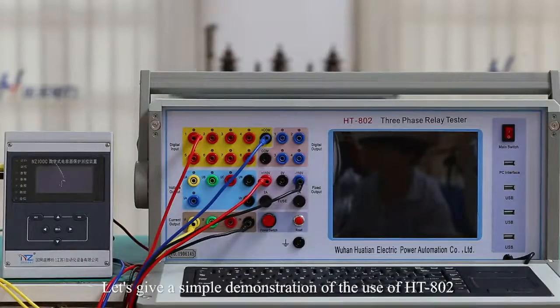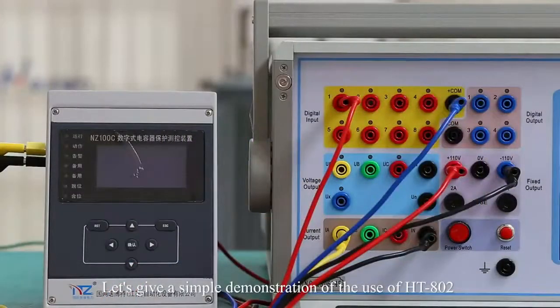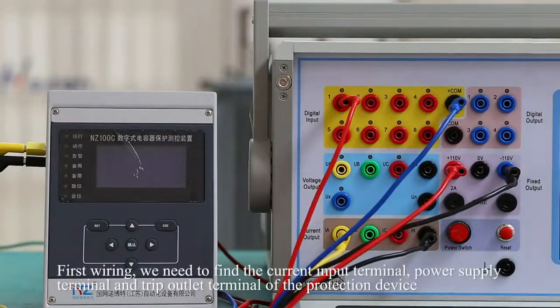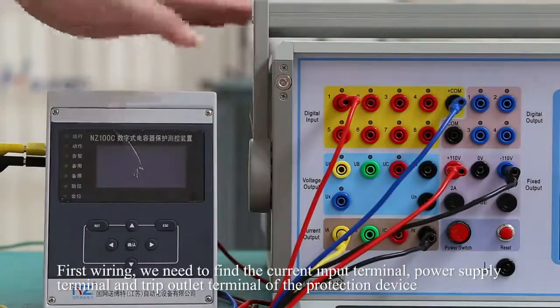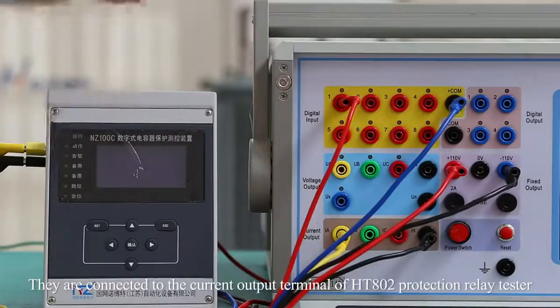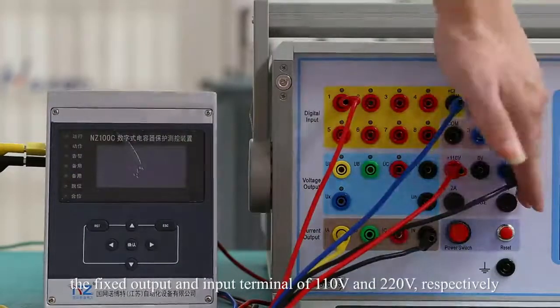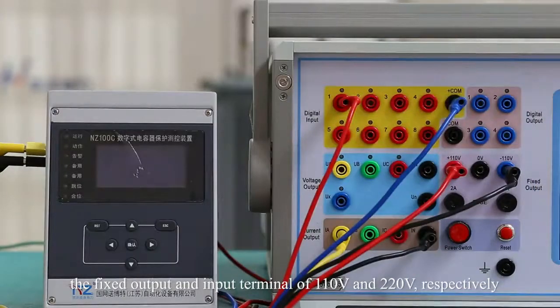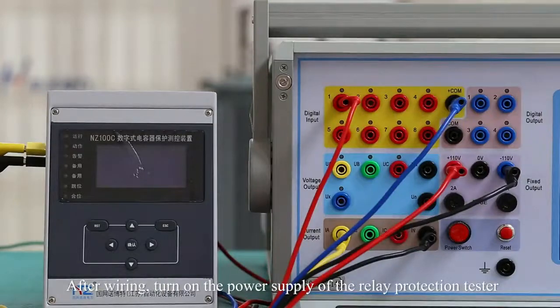Let's give a simple demonstration of the use of HT802. First, wiring. We need to find the current input terminal, power supply terminal, and trip outlet terminal of the protection device. They are connected to the current output terminal of the HT802 protection relay tester, and to the fixed output and input terminals of 110 V and 220 V respectively.